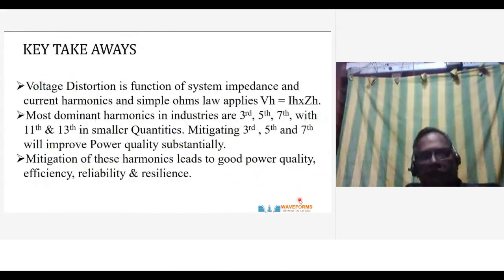So some important things. Voltage distortion is a function of system impedance and current harmonics, and simple Ohm's law applies. V_h is equal to the harmonic current times the impedance at the harmonic. So it could be the third harmonic, fifth harmonic, whatever it is. That is how Ohm's law applies to each harmonic. The most dominant harmonics in industry are the third, fifth, and seventh. Eleventh and 13th in smaller quantities.